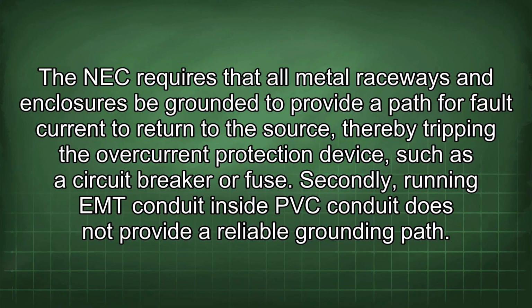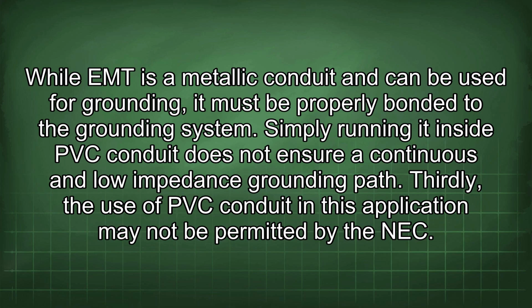Secondly, running EMT conduit inside PVC conduit does not provide a reliable grounding path. While EMT is a metallic conduit and can be used for grounding, it must be properly bonded to the grounding system. Simply running it inside PVC conduit does not ensure a continuous and low impedance grounding path.